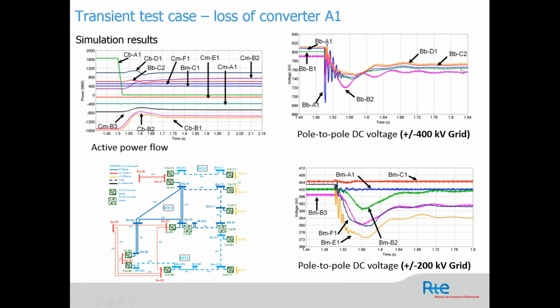The DC voltage here will drop. Why? Because we lost the VDC control, and what remains is the droop control, which will reduce the DC voltage in order to manage the active power. So this is a droop control effect. Here, however, you can see the DC voltage related to Bm-C1. Bm-C1 is this one here, this bus. Since we tripped this one, this DC grid system is separated from the other one, so of course this system should not be affected by the loss of this one, because it's not connected on the DC side. And what you can see here is that the Bm-C1 DC voltage is maintained at its value. Otherwise, the other voltages here will droop because they are in the same DC grid system.